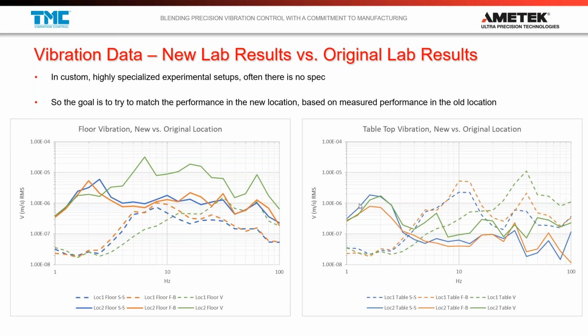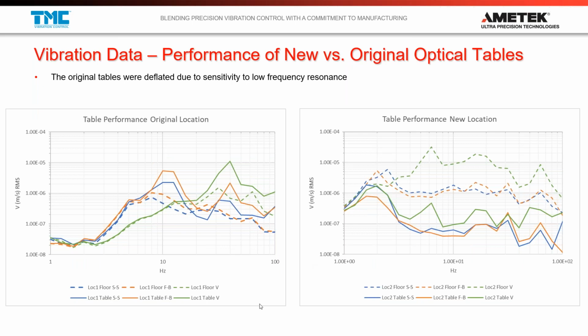So here we have, again, deflated tables in the new location with the new active table. So I'm sorry, this is actually the new tables. In the new location, we saw some input of this floor resonance being knocked down by some percentage. But still that percentage was tolerable.